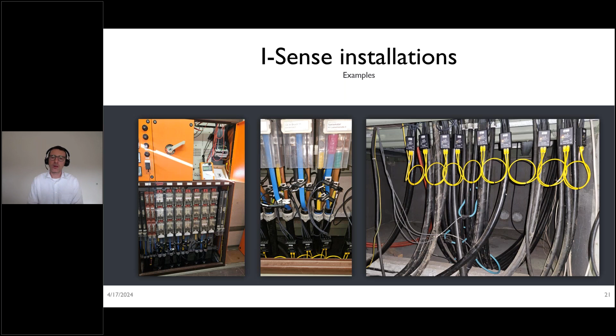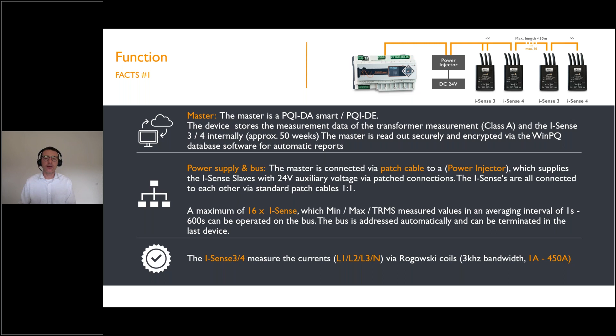So from the main function, our device PQI-DA Smart. We have then a daisy chain with iSense 3, iSense 4, which is also provided by us or could be provided by us. And the master, our technology PQI-DA Smart, is collecting the data from all these devices which are in the depth of the transformer station, so from each feeder. The device can store over 50 weeks of data from all these feeders and so on.